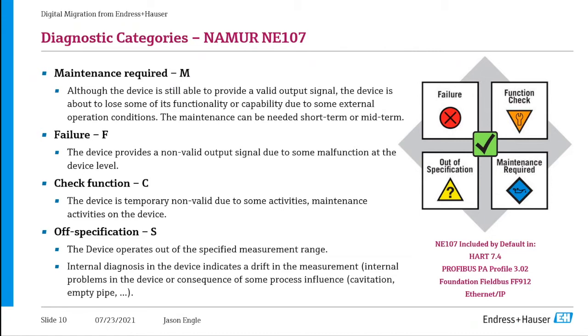If maintenance is required, a blue oil can symbol shows up on the unit's display and within the DCS. If the unit has failed, you get a red box. If you need to check the function, maybe it's out of calibration, you get an orange wrench. And if it's out of specification, you get a yellow question mark inside a yield-sign shape. This digital communication enables heartbeat technology, which allows the customer to use NAMUR NE107 and its diagnostic categories.